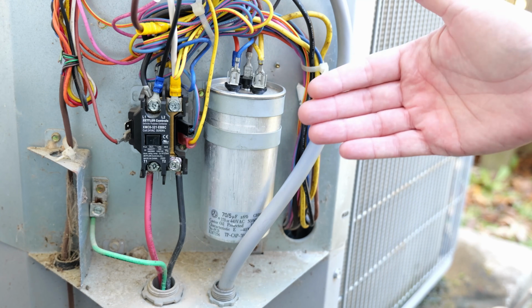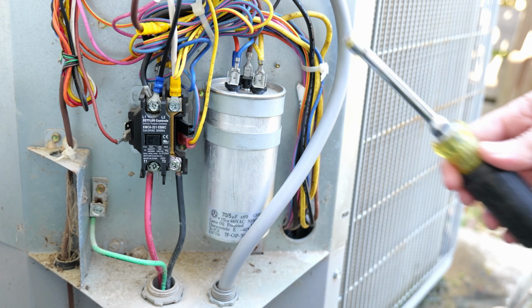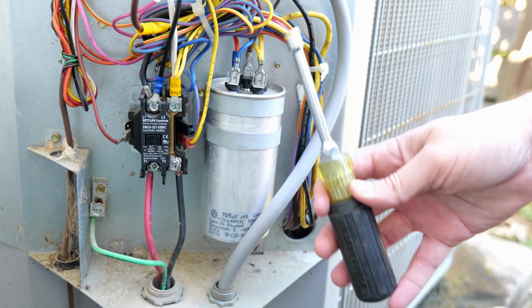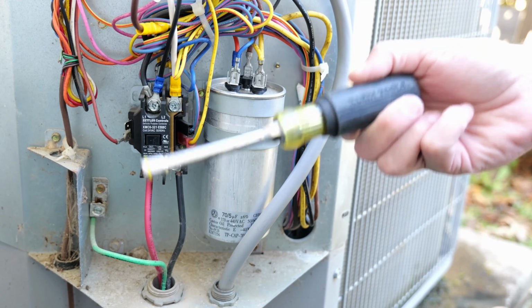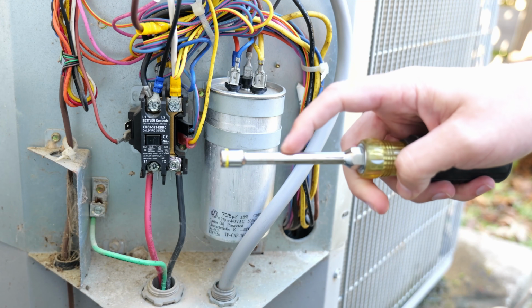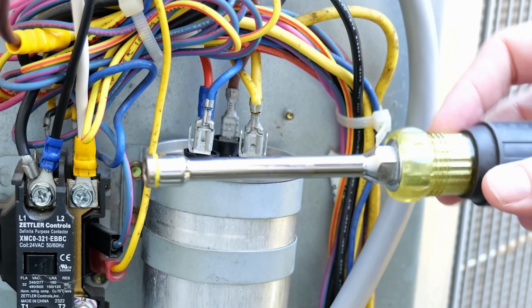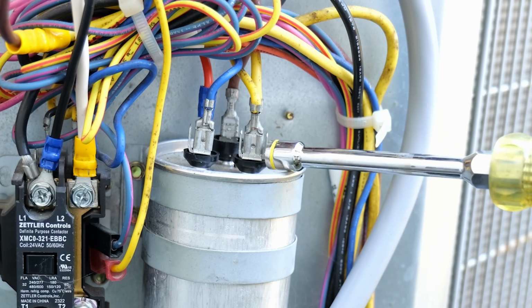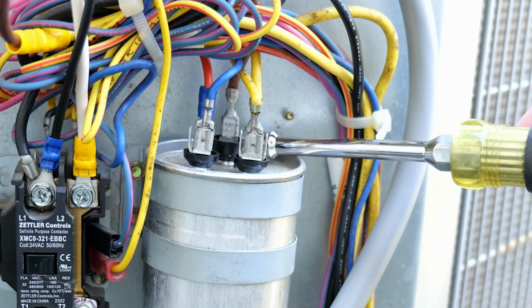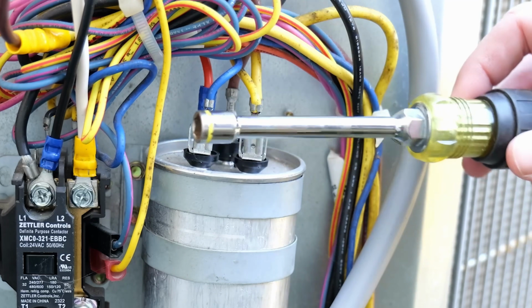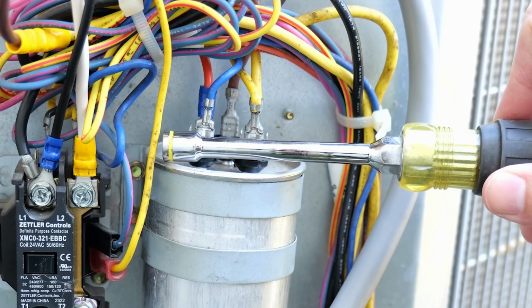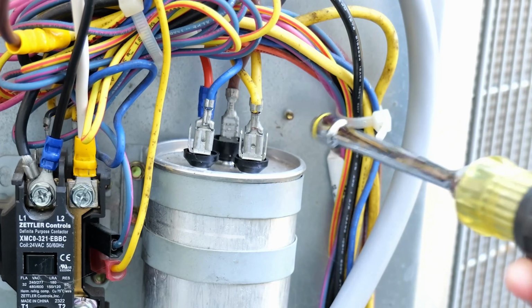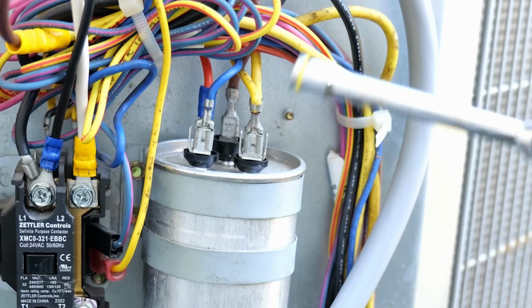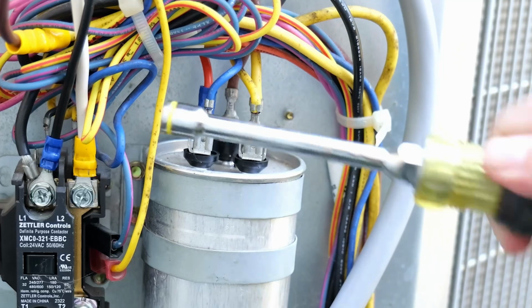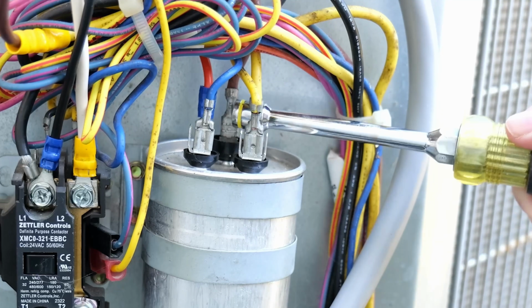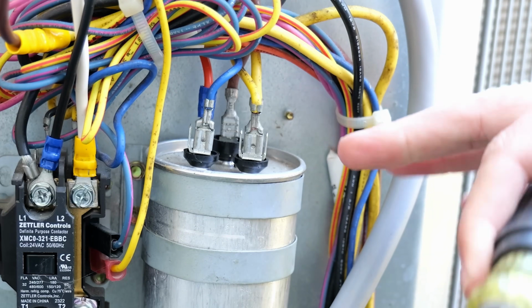And what most HVAC techs will do in order to do that is they will take whatever nut driver or screwdriver that they're using. They will hold on to the insulated end. They will take the metal end of it and they will go from one terminal to the next, where this one over here, this is the common terminal. This is the HERM, and the one in the back is the fan. So what I like to do is first touch to the common, then over to my HERM or hermetic terminal. Then I'll go from common to the fan side, and I will just go back and forth a few times just to make sure that this is in fact discharged, so I don't receive any kind of a shock.